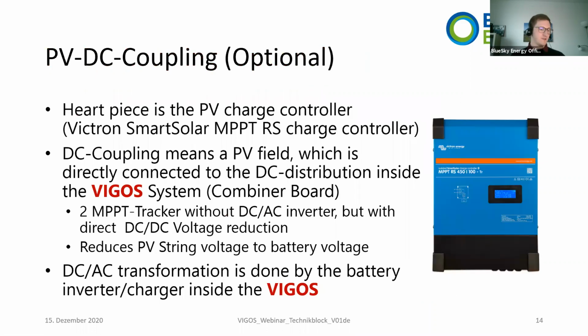Then we already get to the first option, the PV DC coupling. This is an optional function. The heart piece of this is the PV charge controller. The Victron Smart Solar MPPT RS charge controller is a DC-DC charger, and a DC coupling for us means a PV field which is directly connected to the DC distribution inside the Vigos system. Inside this DC charger, you have two MPP trackers without a DC-AC inverter. So it's only a DC-DC voltage reduction, and the DC-AC is done by the battery inverter, the Multiplus-II devices. So the DC-AC transformation, as you can read here.